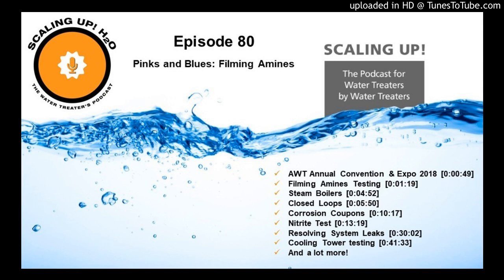And of course, since we were running that test and they knew that we were running that test, they didn't want to skew any of our data, so they called us the second that it happened. I know you're laughing because that did not happen. Folks, we found out about this leak when we came back 2 weeks later. So now this is supposed to be 2 months into the test, and we had absolutely nothing in the system, and the system was orange in color.